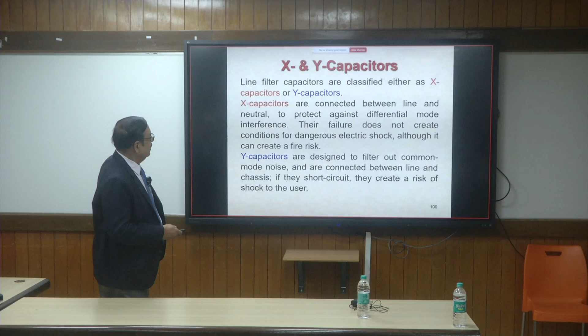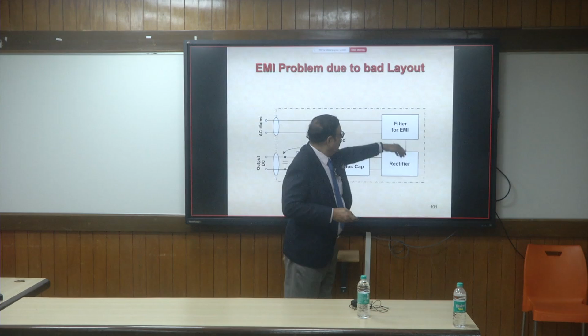This is a very bad example of bad equipment design. Here my AC mains comes in. I have put an EMI filter here, then a rectifier, a DC bus, and a switching circuit goes out. I have put a filter, so I presume that all the interference created here is not going to go out to the lines. But the catch is the wiring inside. All the switching circuit radiation gets picked up here and gets conducted into the AC mains. So when you have a test, you'll find all the interference is here.